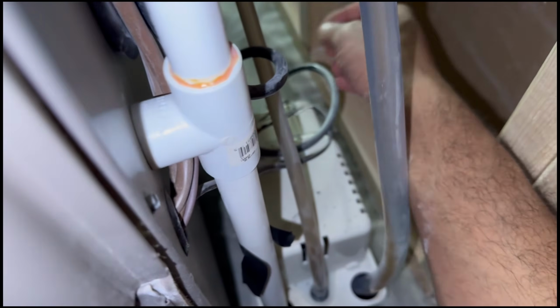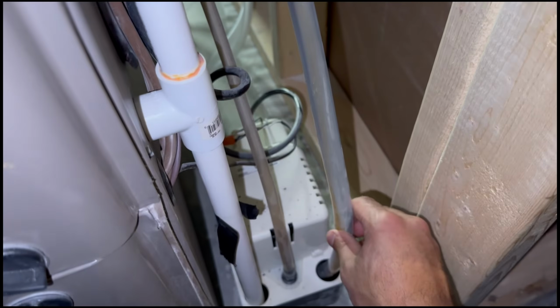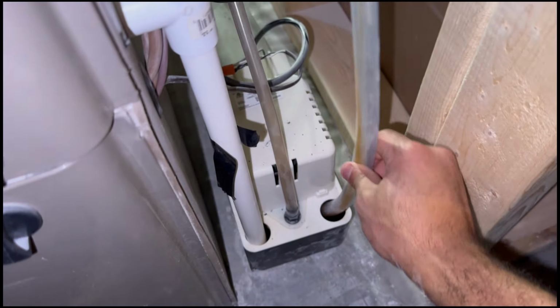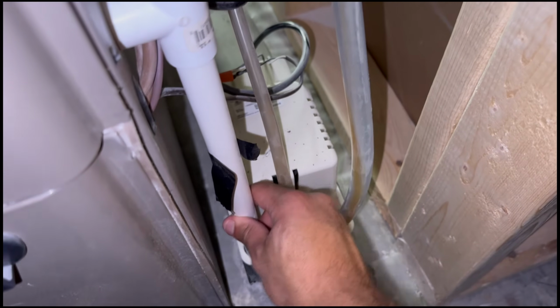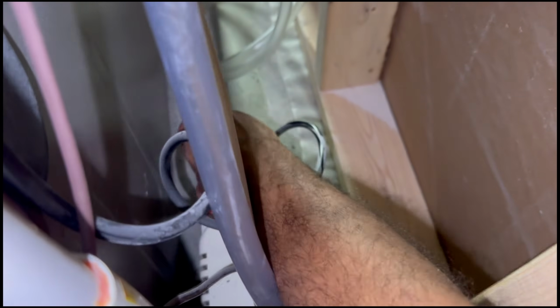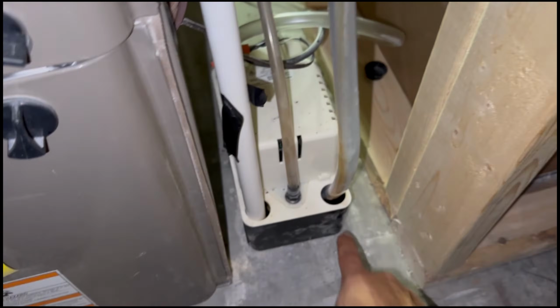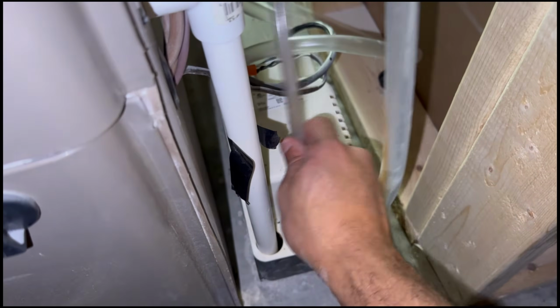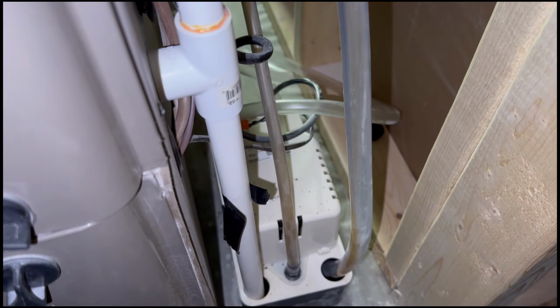This is my draining unit, and you'll see that this one is coming from my furnace, or rather this one is coming from my air conditioner. This one is from my furnace, and I have one extra port at the back here. So I'm going to remove the plug, and I'm going to take my drain hose and I'm going to put it into the unit just like that. I'm probably going to cut that hose a little shorter, but you'll see now I'll be draining right into this unit. And what happens with this unit is when the water level gets to a certain height, it will pump it out and it'll send it to the drain, which is located across on the other end of this room.